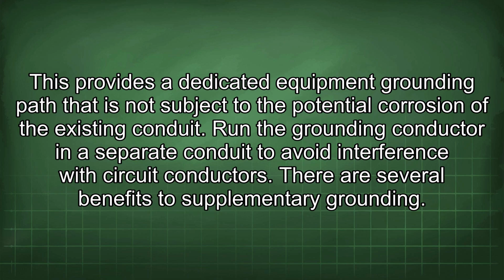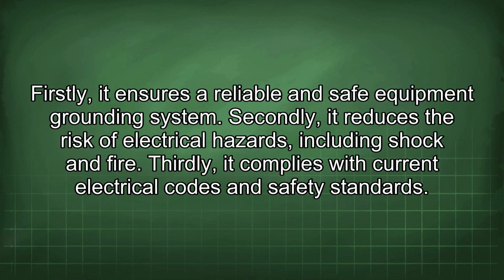Run the grounding conductor in a separate conduit to avoid interference with circuit conductors. There are several benefits to supplementary grounding. Firstly, it ensures a reliable and safe equipment grounding system. Secondly, it reduces the risk of electrical hazards, including shock and fire. Thirdly, it complies with current electrical codes and safety standards.